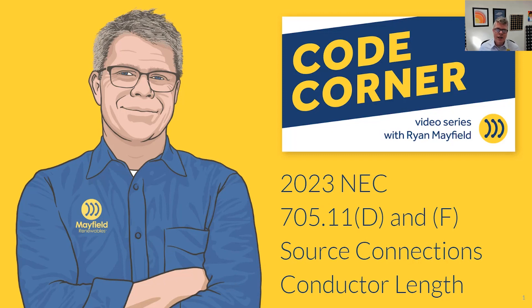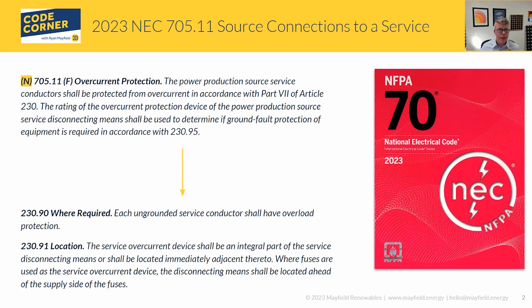The topic is around the length of conductors. For those of you familiar with 705.11 in the 2020 code, we had some limitations on the length of our conductors for supply side connections. In the 2023 language, those are gone. So now we have to figure out what we're left with. Let's jump in and look at some of that code language.